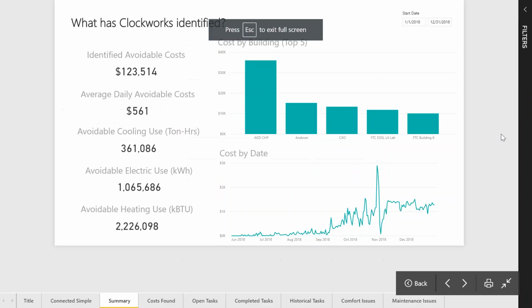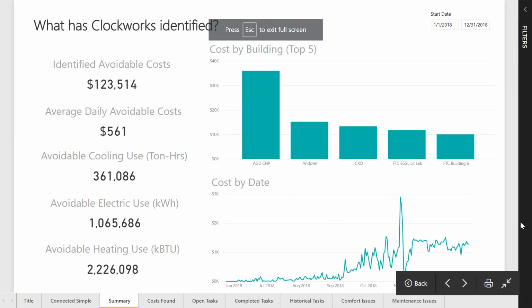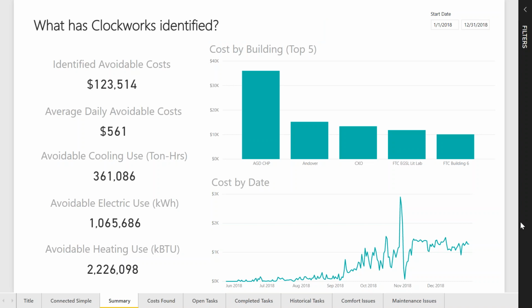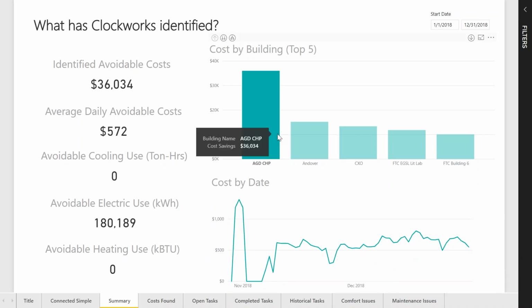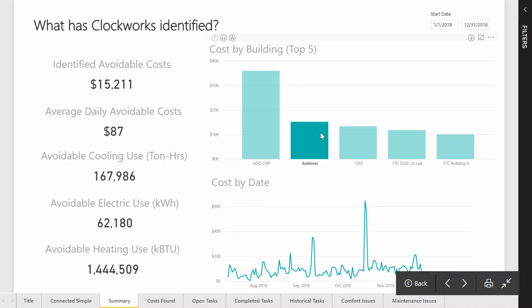I'm going to pull up a report. What we're looking at is actually Power BI. It's a business intelligence dashboard. There's an API that's pulling data out of that Clockworks platform into this flexible reporting engine. So I've gone from the weeds of the leaking valves and the stuck dampers up a level to really an executive level summary of what's happening on campus. So the first thing is what's really been identified and how does that break down by building? Where are we finding the most amount of issues? And if we click on buildings here, we can actually see specifically what's going on and everything dynamic here in terms of the excess cooling use, electric use, heating use that are being identified.